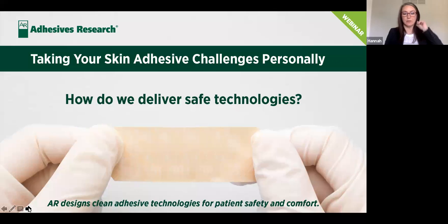The second question I wanted to address was, how do we deliver safe technologies to your patients and customers? And the answer is through clean adhesives. So what does that mean? Fiona is going to share a lot of detail today about biocompatibility, which I know is a critical requirement for many of these products, but there's more to it than just passing a standard test. In addition to careful study and selection of non-sensitizing materials, we have developed processes that significantly reduce residual monomers, or the leave-behinds that can cause skin irritation, discomfort, or even allergic reaction. These methods are applied to skin adhesive development as well as device bonding adhesives to minimize risk and maximize patient comfort.